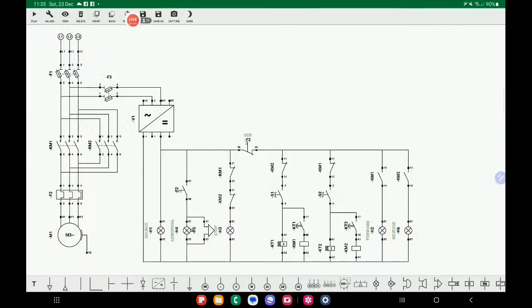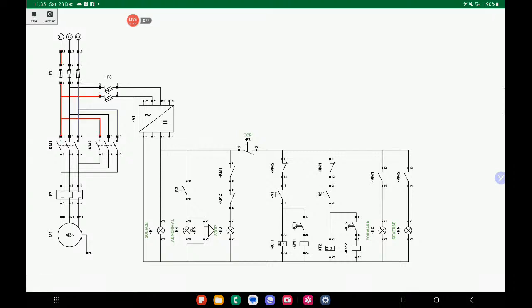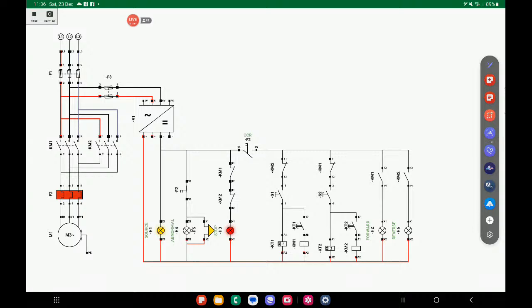the condition of your circuit would be like, let's say we will run it. Okay, this is the condition. I run the switch 1 forward operation, and then my F2 tripped. So while it is tripped, this would be the alarm and this would be the condition. As you can see, in this situation, you have an open OCR, right? The abnormal alarm is lit, the system is stopped, source is on. So it only means that you're having an overloading onto your system, short circuit, or a single phasing. This could be the possible situation because your overload relay is activated.